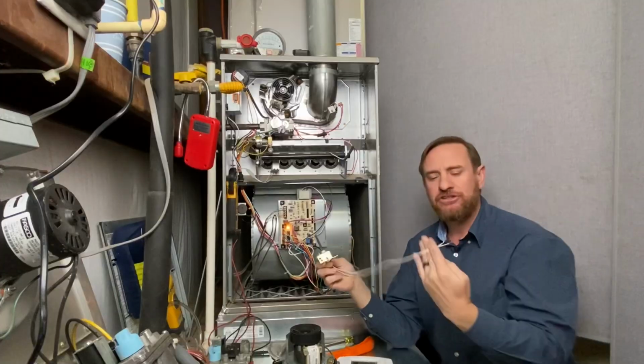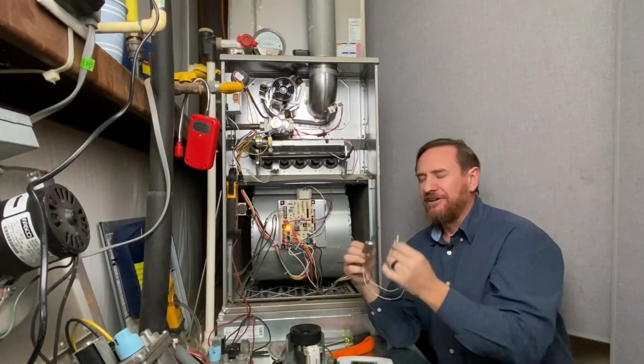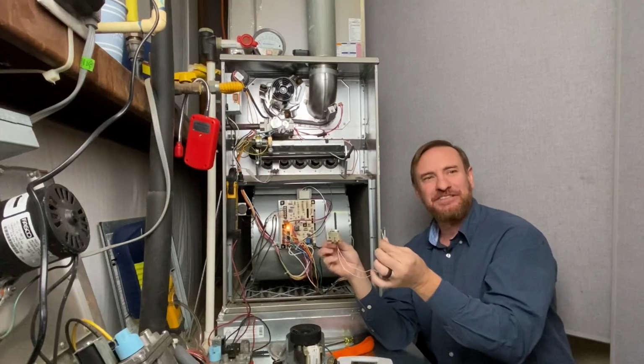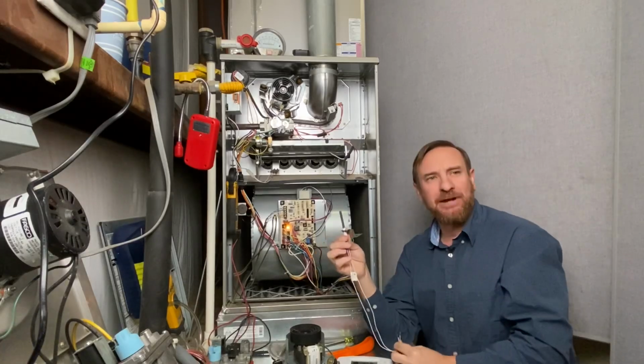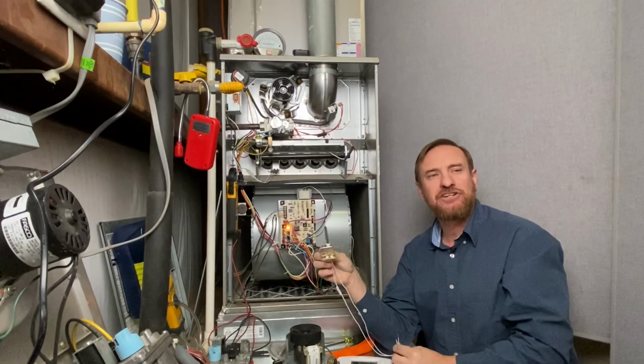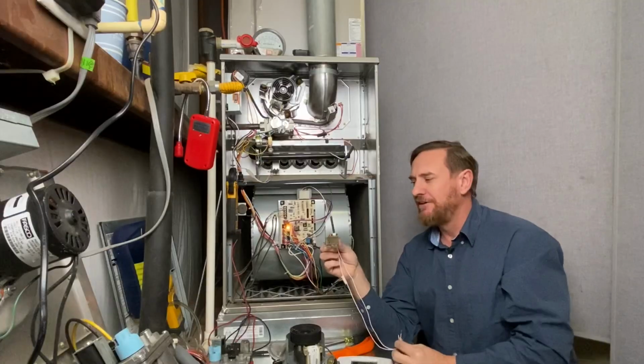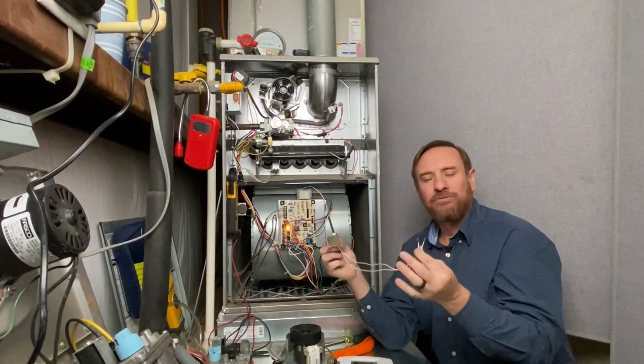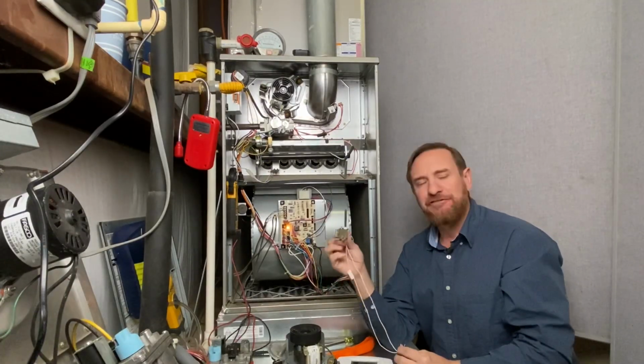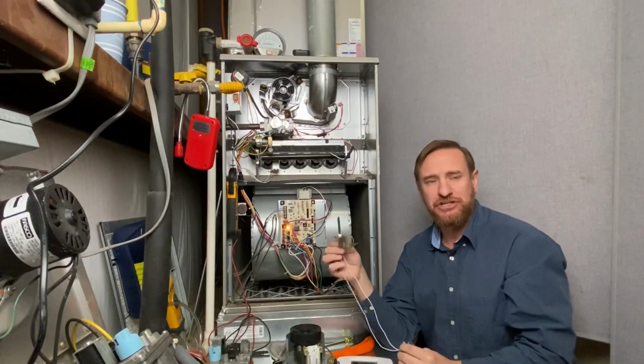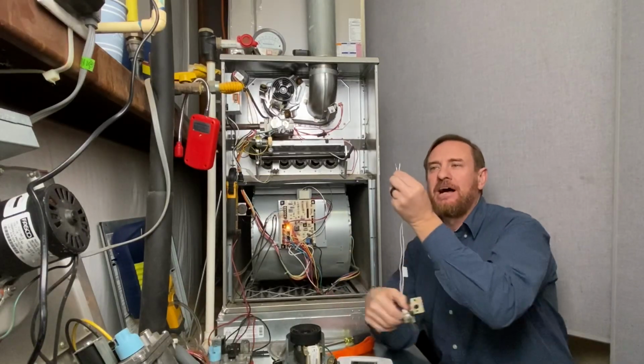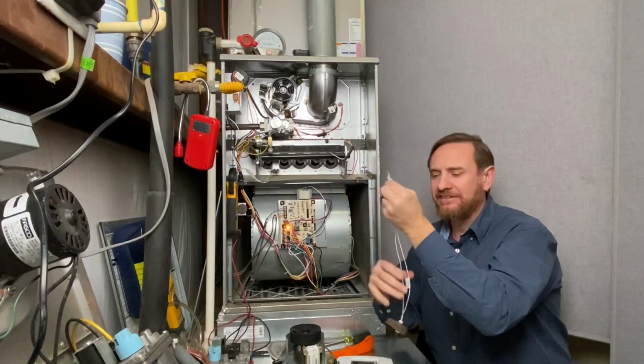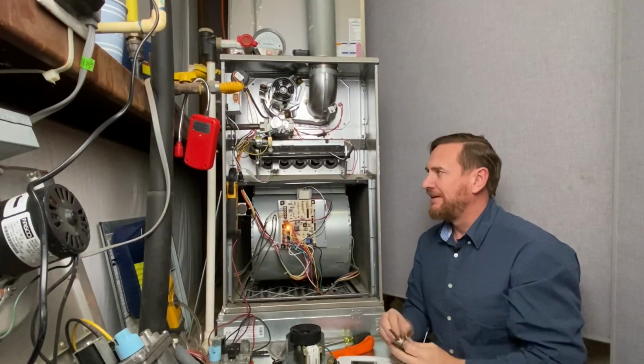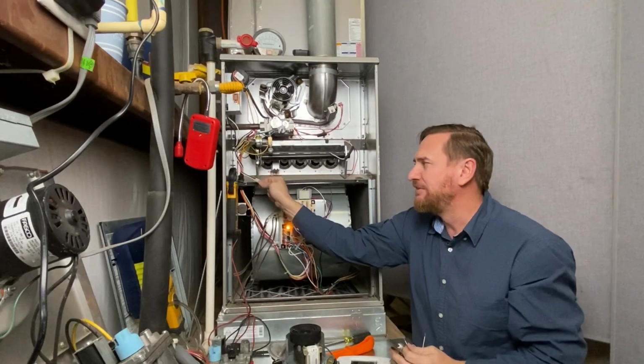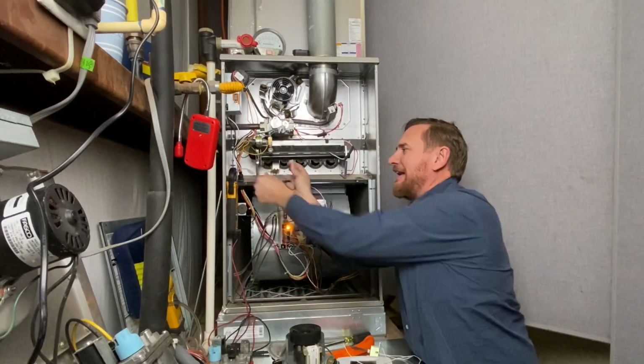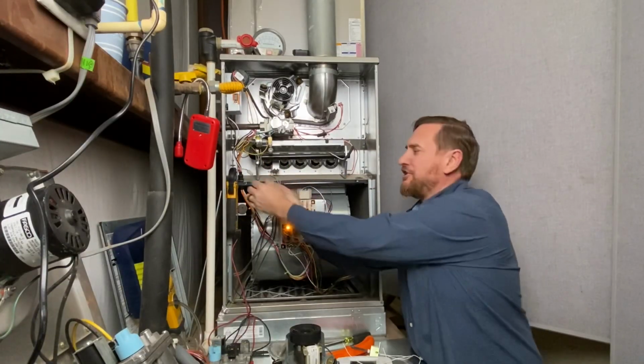We used to teach to ohm out these pressure switches. We used to teach to ohm out these hot surface igniters. The problem is there's so many different brands out there now and so many different manufacturers that have a variety of different ohm readings that they want on these. It's really not an accurate way anymore. You'd have to find out from every single manufacturer what the resistance should be and what the allowable is to know. I'm still old school. I like to ohm these out to see what my readings are, but it's really not as necessary. Remember, if you're going to ohm it out, you need to disconnect the component entirely. Now it's isolated. Now I can use ohms and check this.